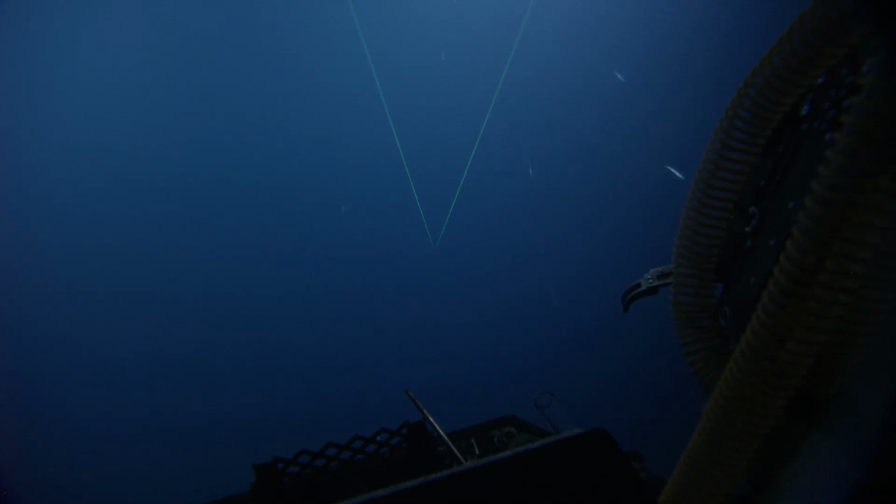Then the parameter you're really going to want to check to make sure the instrument is happy is inlet gas humidity. Is that going to change color if it gets unhappy? It doesn't change color, but it will get really high. Usually in a dive, yesterday was at like 20%. That was good. 40% fine, 50, 60. If it gets to like 80%, then the humidity is getting high, and there might be a reason for that. In this region where there's nothing hydrothermal, the most likely thing is the pump isn't working great.